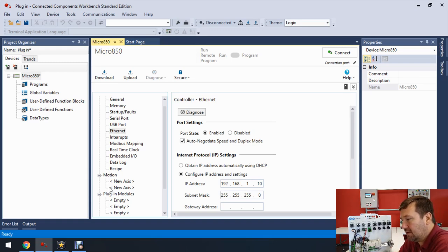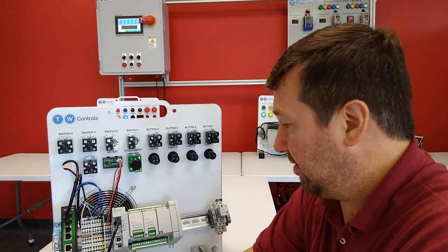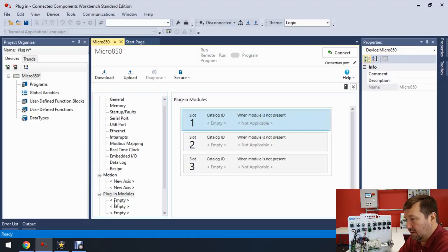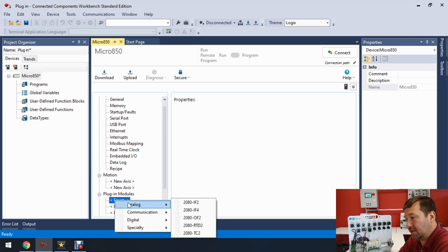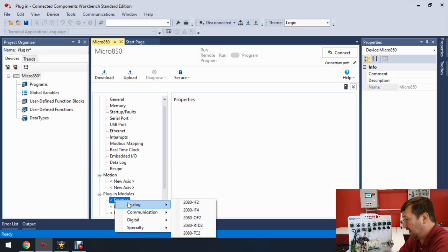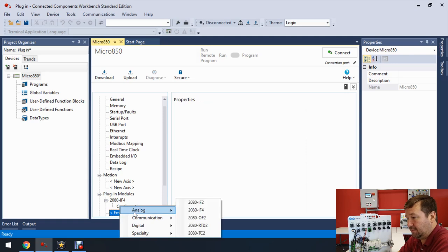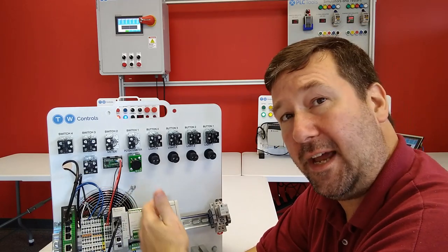Now go down to our plug-in modules — we see three slots, which coincides with the three physical slots. Click on the first slot where it says 'empty', right-click it, and select 'Analog' because this IF4 is a four-point analog input. Then right-click the next one down, select 'Analog', and choose the OF2 — so that gives us our four analog inputs and two analog outputs.